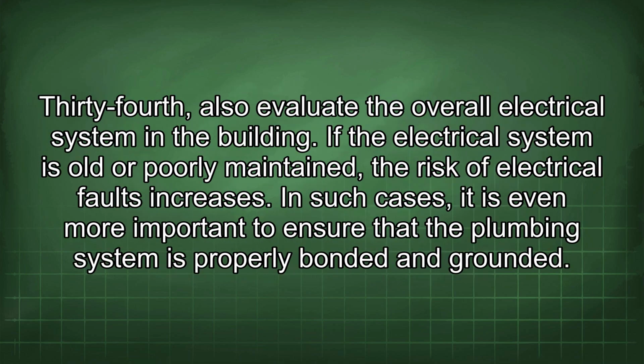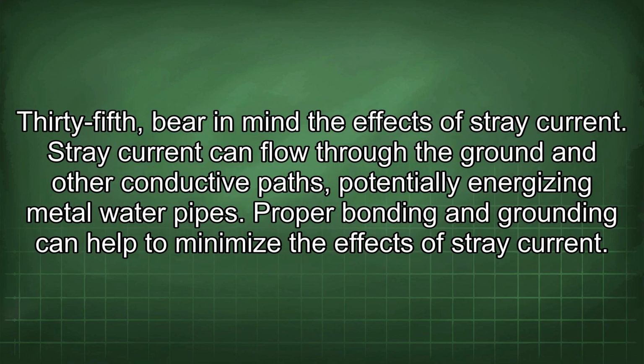34th, also evaluate the overall electrical system in the building. If the electrical system is old or poorly maintained, the risk of electrical faults increases. In such cases, it is even more important to ensure that the plumbing system is properly bonded and grounded. 35th, bear in mind the effect of stray current. Stray current can flow through the ground and other conductive paths, potentially energizing metal water pipes. Proper bonding and grounding can help to minimize the effects of stray current.